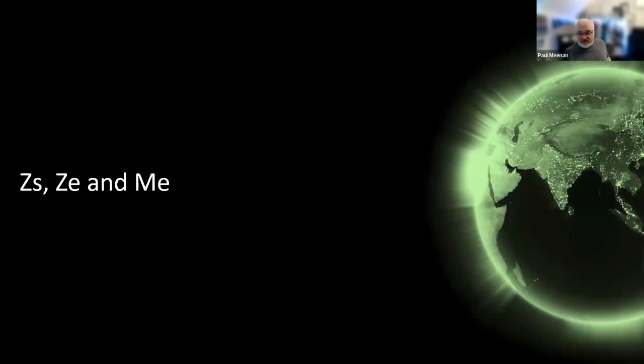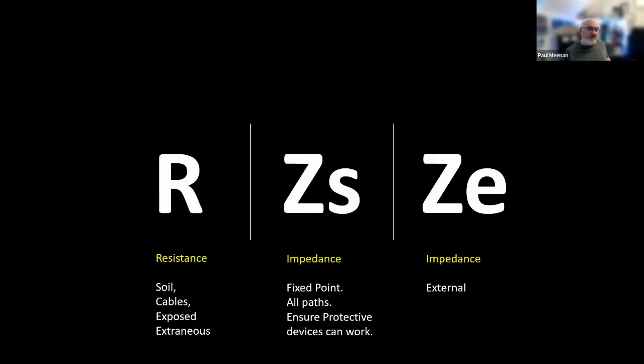Now, one of the key things for earthing and bonding to its success is ZS, ZE, and Me, which is the phrase I use. In electrical installations, again, if there are any learners on here, I break it into 3 concise parts: resistance, impedance, ZS and ZE. Resistance, we look at the resistance when we're looking at earthing, of the soil, of the cables, of the exposed parts, of the extraneous parts to prove safety.